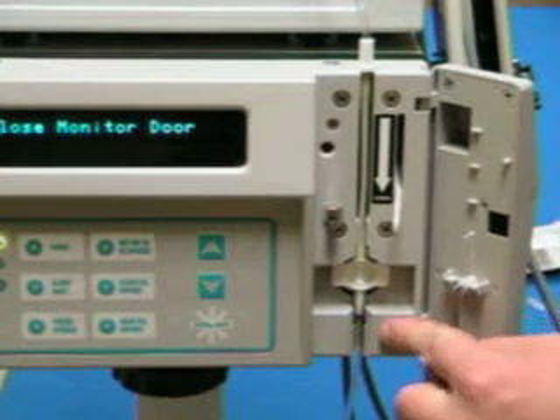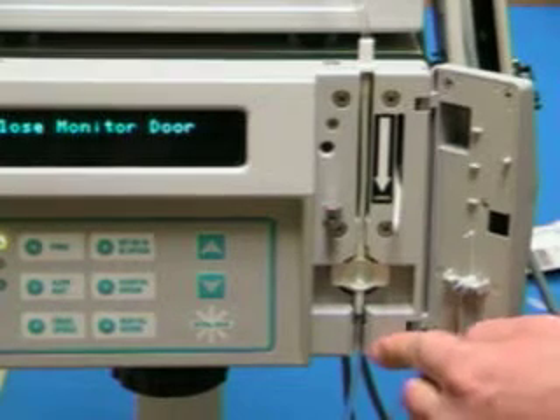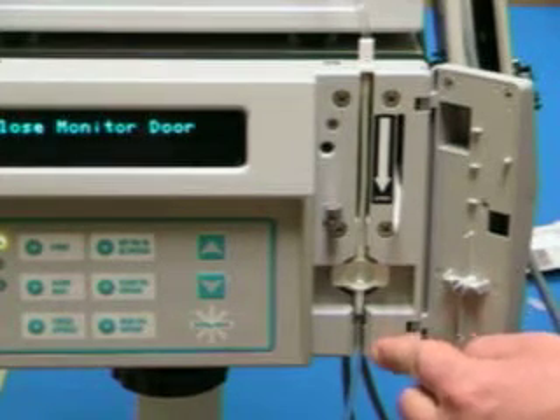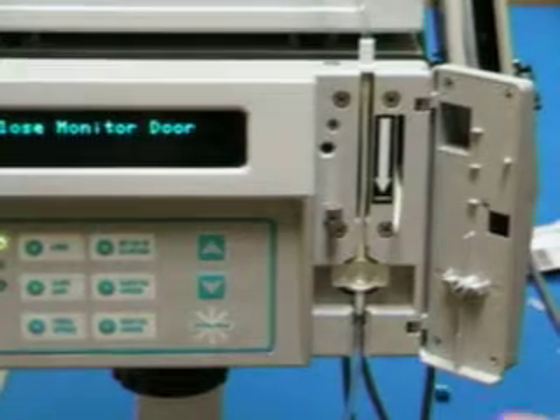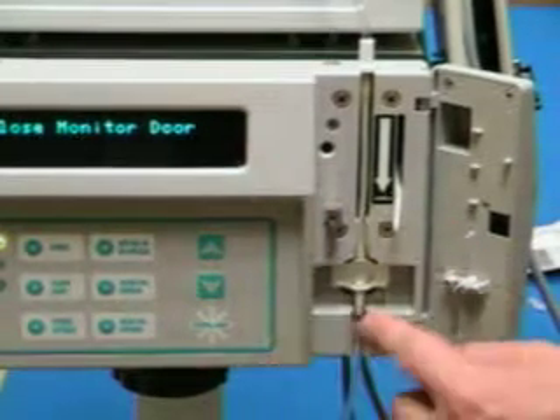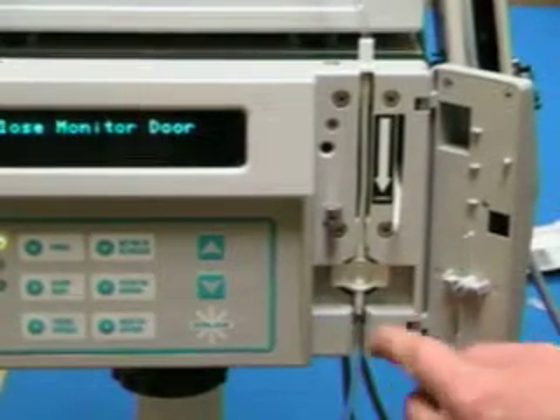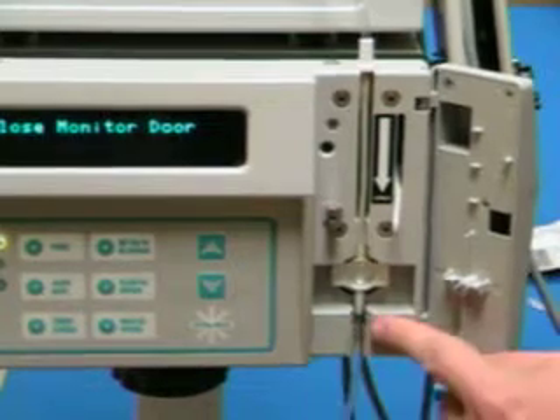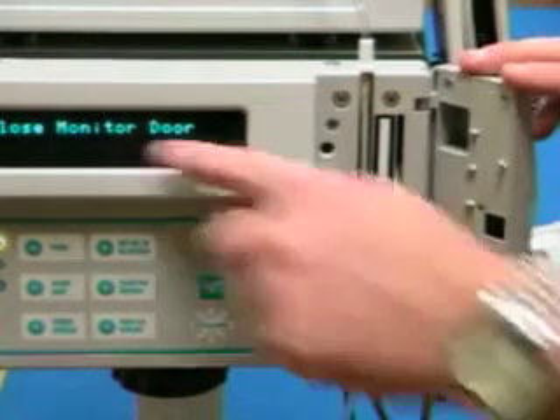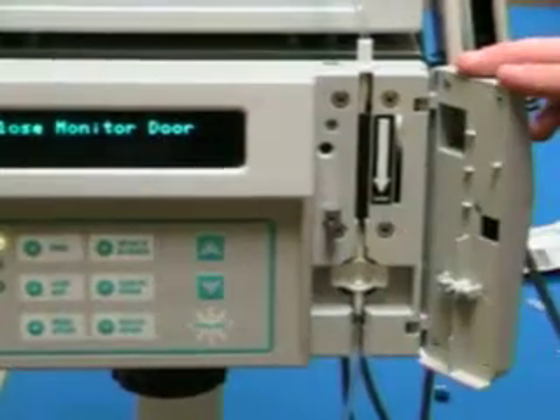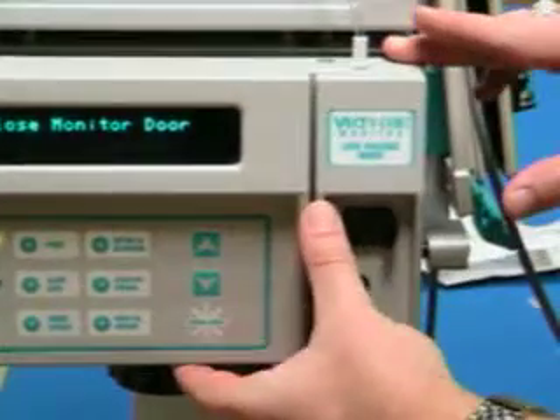It'll give you a false reading, but that's where it senses if there was actually air in the line at that part. You'd get an air in line warning here. Now if you ever got that warning and you knew you didn't have air in your line, then those sensors are dirty, so you got to clean those with an alcohol swab. So to close the door like it's telling you to, flip the white lever up and shut the door.